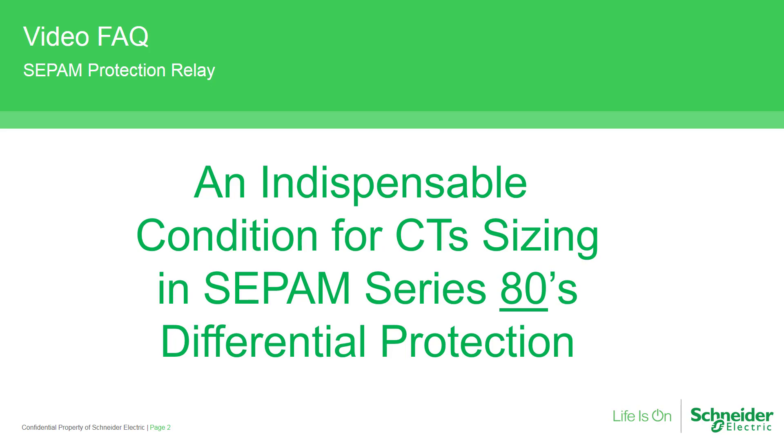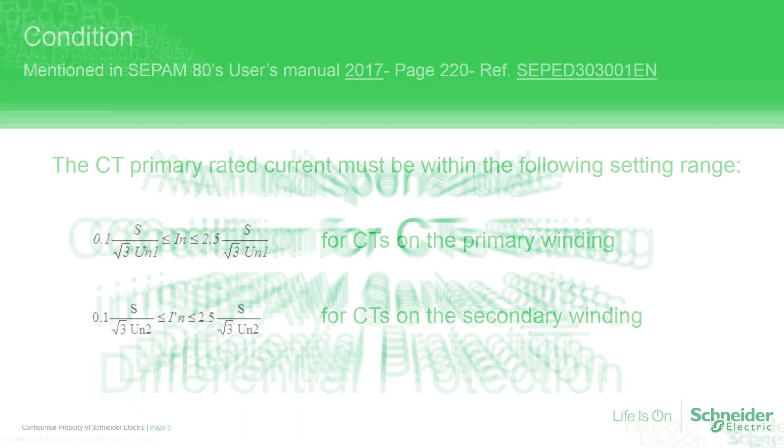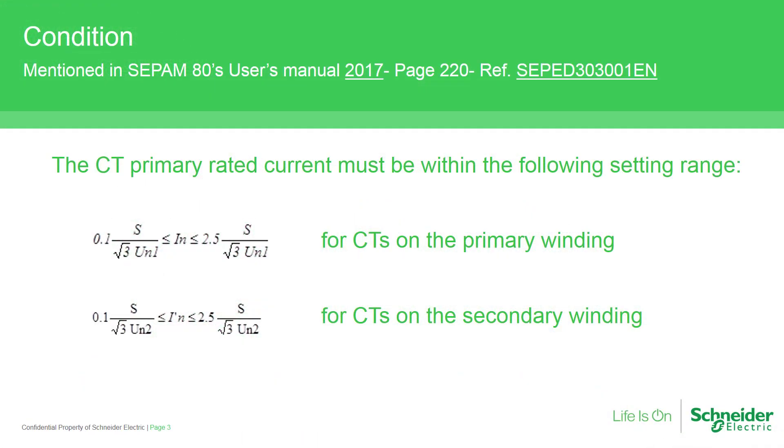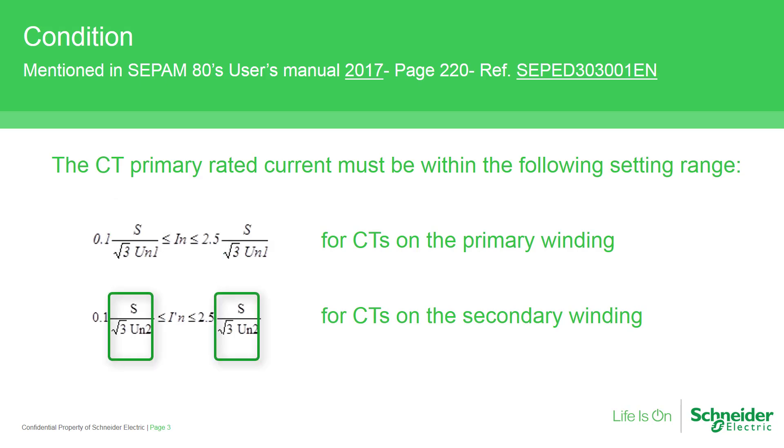These conditions are clearly explained on page 220 of protection metering and control functions user manuals SEPAM series 80. First, nominal current or base current of power transformer should be calculated on both sides, I mean both primary and secondary windings. The primary rated current of CTs should be sized between 0.1 to 2.5 of calculated current.